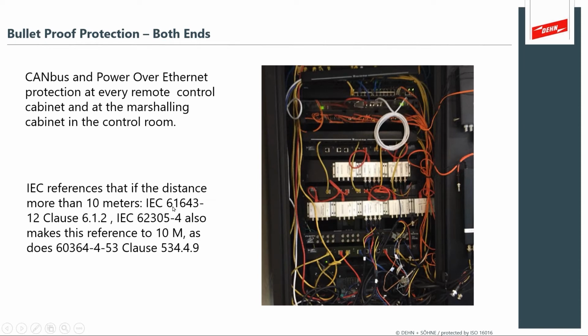As I mentioned, the IEC standards dictate that surge protection devices should be installed if there's a run longer than 10 meters. And of course, on a very large power generation facility, you'll have extensive runs of data collection and CAN bus control systems. These are distributed networks that span the entire plant, so it's very important to have surge protection devices installed on both ends.